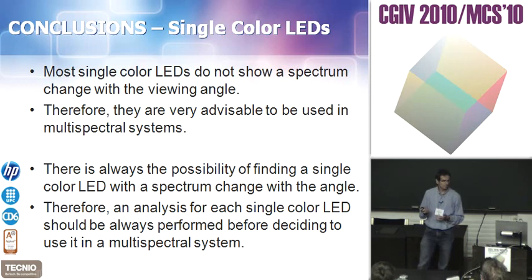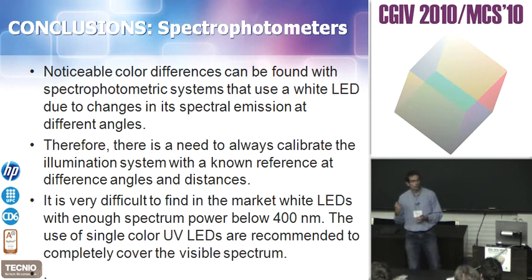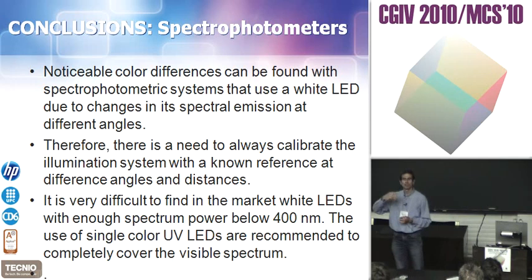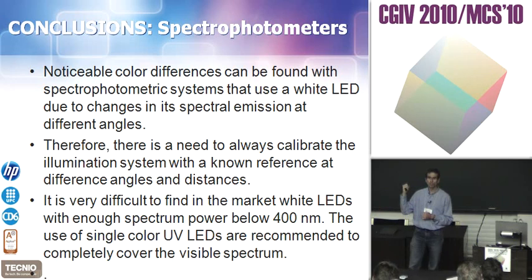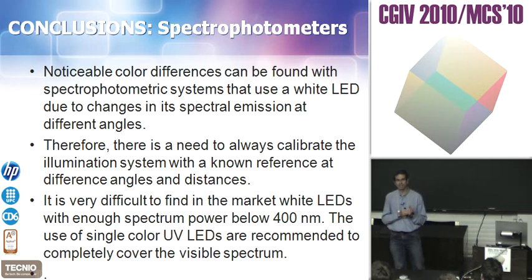Regarding spectrophotometers: those using white LEDs as light sources should be calibrated at different distances and different angles if we don't want bad color accuracy measurements. If you have a system where distance and angle don't change — like a contact spectrophotometer — you won't have any problem. But if the distance to the sample changes, using a white LED as a light source can cause bad color accuracy. Also, white LEDs alone don't have power below 400 nanometers, so if you want a spectrophotometer covering 380 to 730 nanometers, you should use white LEDs in combination with UV color LEDs.